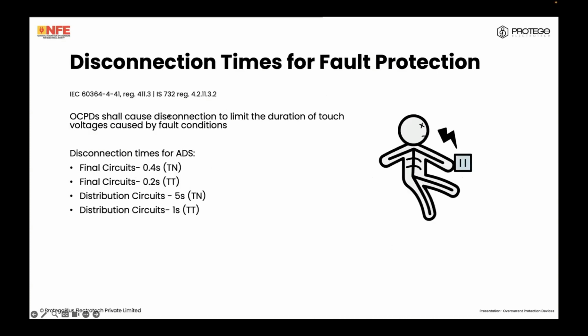We all know that if you look at IS 732 regulation 4.2.11.3.2, the OCPD shall cause disconnection to limit the duration of touch voltage caused by fault currents. For final circuits in TN systems, this is 0.4 seconds. For final circuits in TT systems, this is 0.2 seconds. For distribution circuits, this is 5 seconds for TN systems and 1 second for TT systems. The ADS will only limit the duration of the fault. The bonding will limit the magnitude.